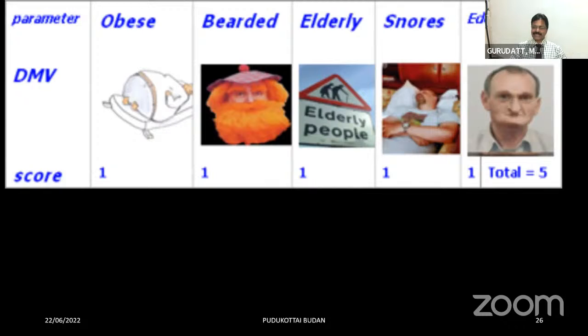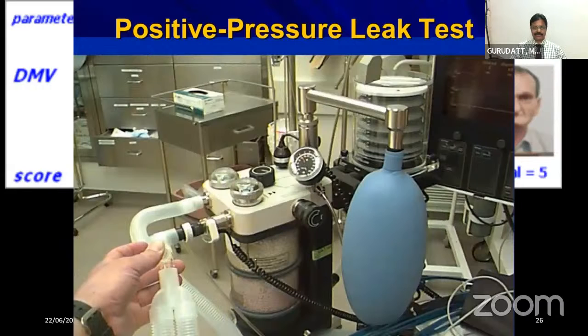It's a safety mechanism that is present in all the machines and the workstations. So you can definitely use it when you are finding difficulty in mask ventilation, or if you want to give 100% oxygen under higher pressure to the patient, then also you can activate the flush. The other time when you use this oxygen flush is when you are checking for the positive pressure leak test. You can pressurize the whole system by activating the flush.